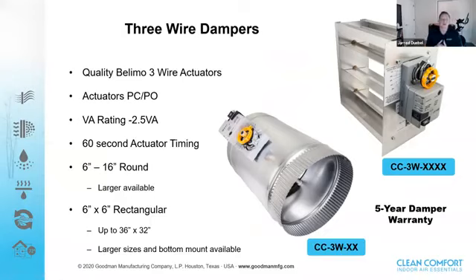Now, we had a question the other day. Someone said, well, hey, if there's an existing 3-wire damper and I want to stick an ESP panel on it, can I? And I said, absolutely. So long as it's a 2-position floating point, especially if you know it's a Belimo actuator. Timing's irrelevant because the logic that's built into the panel does not require anything specific as far as the timing's concerned. The only time we've ever ran into an issue is the way a Carrier Infinity actuator works. It's a little bit different. So if you run into that type of situation, give us a call on tech support and we will walk you through what you will need to do.